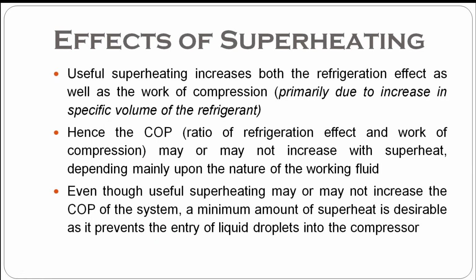Now the effects of superheating. Useful superheating increases both the refrigeration effect as well as the work of compression. Both are increased due to useful superheating, primarily due to the increase in specific volume of the refrigerant. Specific volume of the refrigerant increases due to superheating. Again, visualize that from the diagram. Hence, the COP may or may not increase because both the work of compression as well as the refrigeration effect are increased. So COP may or may not increase depending on the relative values of increase.